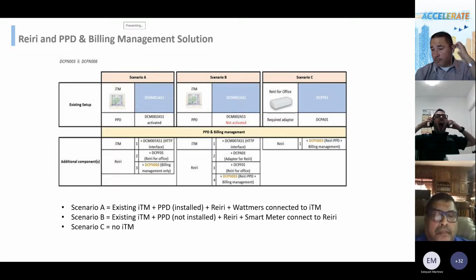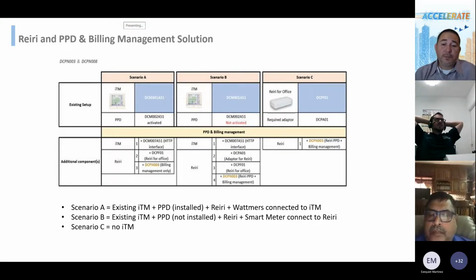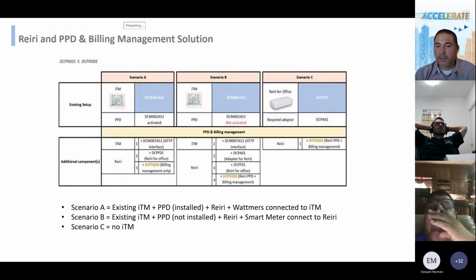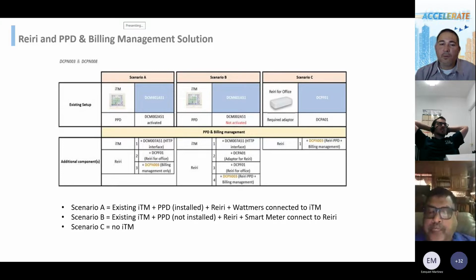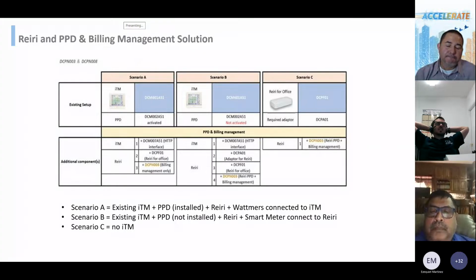Honestly, I'm going to be very clear. The REIRI is taking over the iTouch Manager because it can handle up to 2048 indoor units. That's a little more than the iTouch Manager. But the iTouch Manager is still a good option if you're going to use BACnet, if you're going to use it as a BACnet client. And in BACnet client, which is another language by the way, the REIRI is Modbus, and iTouch Manager connects to BACnet.